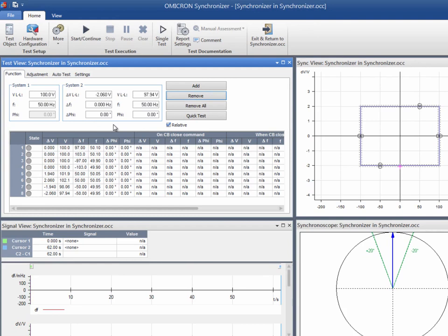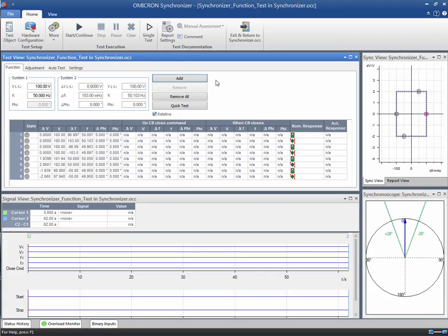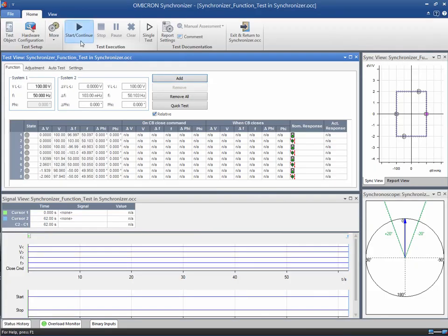For the test points within the synchronizing window, the relay should issue the circuit breaker close command. For the outside points, the synchronization is not possible. Now we press play to run the sequence of test points.